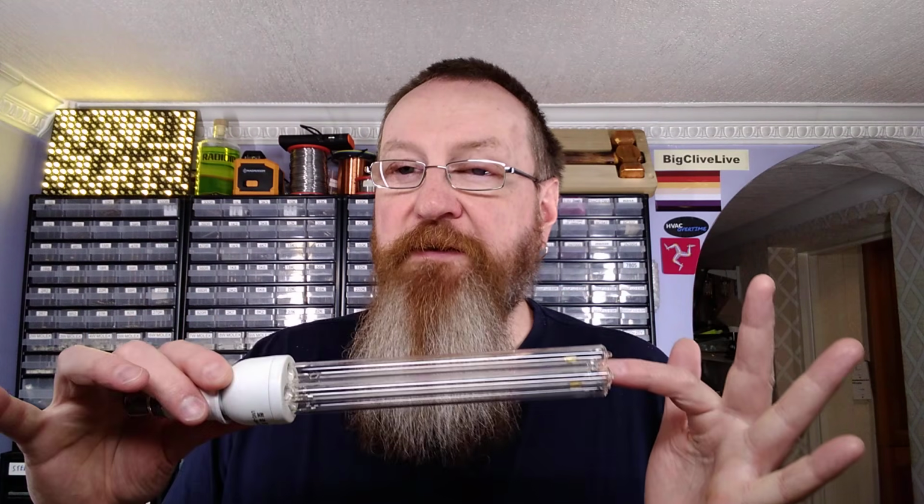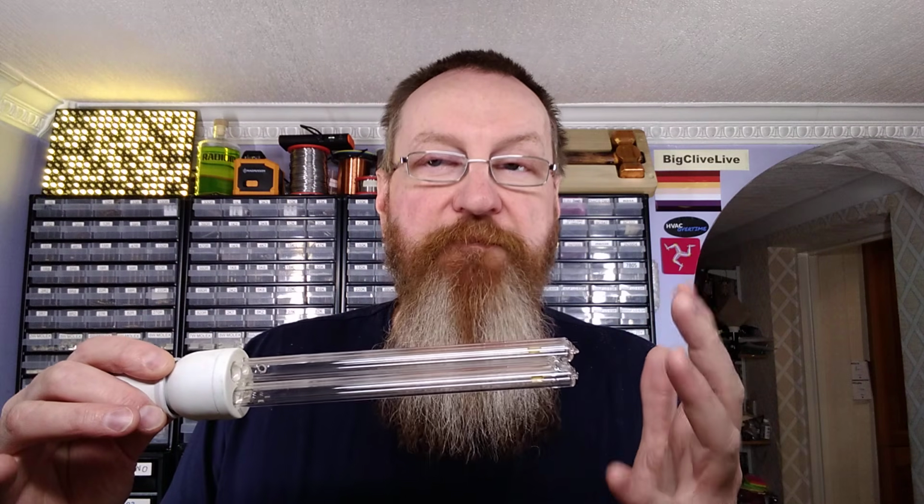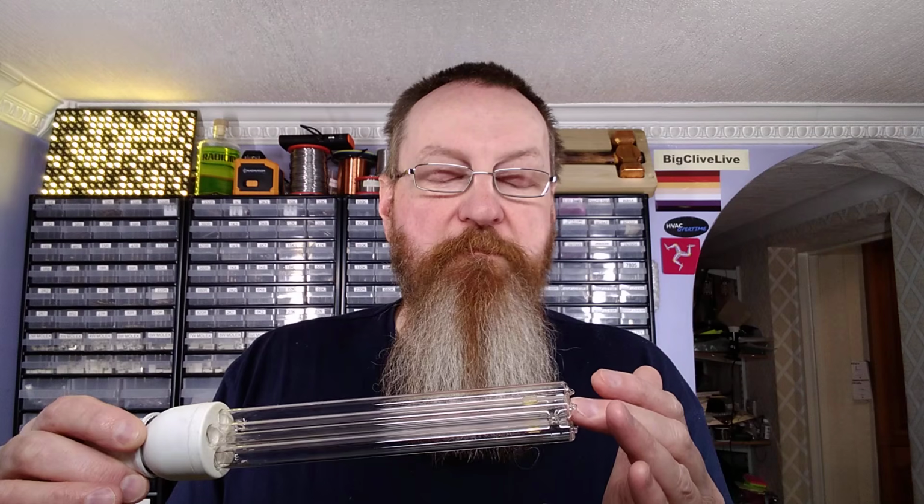With an airflow through these, it's worth mentioning you can't expose your skin to these when they're lit, because it causes skin irritation and eye damage, like an arc flash from welding. But in the catering industry, they do like these because it's a very convenient, known, consistent way of producing a certain amount of ozone, even if it's less efficient. That consistent output is quite useful. It means they get a predictable quantity, and all they have to do is change the tube every so often, so it makes it a fairly maintenance-free application.